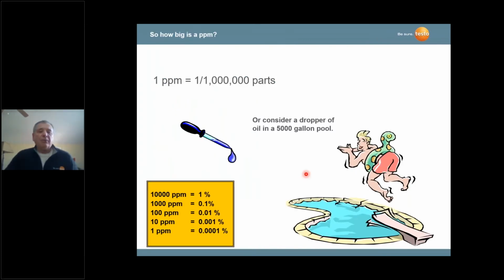We measure carbon monoxide in ppm, down to 1 ppm. That's why the CO cell sensor is calibrated periodically on a concentration of carbon monoxide. Typically, you can measure down to 2, 3, 5 parts per million CO. And it's important to do that because we're using these analyzers in the flue gases, as well as they can be used in checking ambient air conditions.